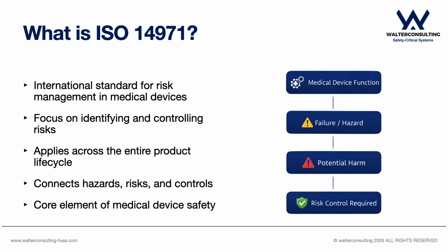ISO 14971 defines a structured approach to identify hazards, evaluate risks, and control them. It connects these elements into one consistent process. And this process does not stop after development. It continues throughout the entire life cycle. This is what makes it so important. It is not just a method. It is the foundation of safety in medical devices.